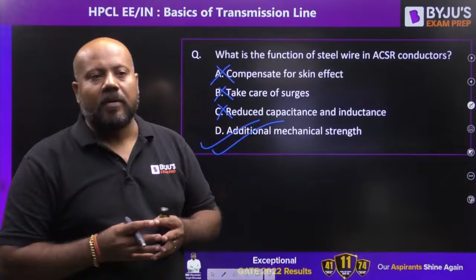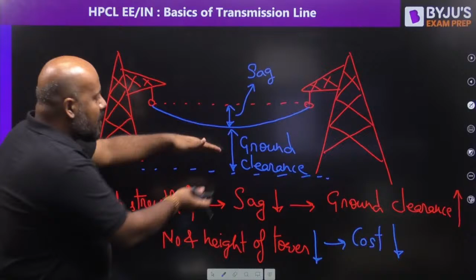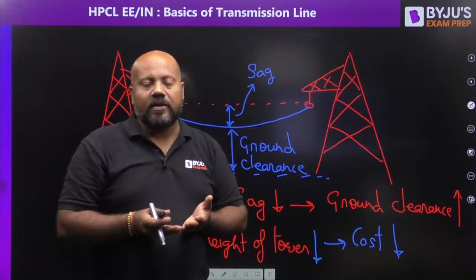See what is happening. We are operating our transmission line at a very high voltage, so there must be a minimum ground clearance. Now, if by using the ACSR conductor you are getting higher mechanical strength, then the drop in the conductor shape, the sag, is going to be less. When sag is less, ground clearance is going to be more. When ground clearance is more, it means the height of the transmission tower and the number of towers is going to be less. Yes or no? Just use your common sense, you will understand.